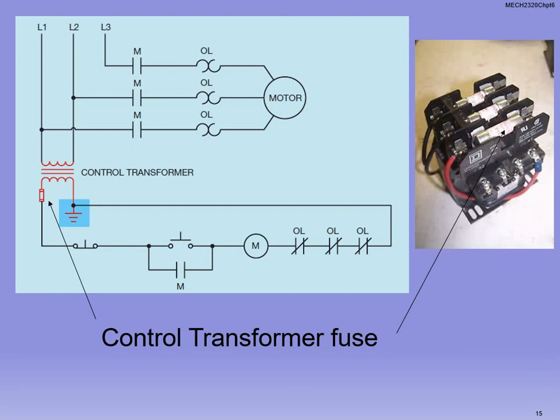And this isn't necessarily a complete diagram, but I kind of want you to start seeing how everything is pieced together. Okay, notice the push button on the bottom part of the schematic here, the push button that's tied to contactor M. That M is the same contactor that's at the top of the schematic that's normally open for line 1, line 2, and line 3. Because when you push that button, you're closing all 3 contactors at once. All right, so that applies to the last lecture where we talked about those sort of things.